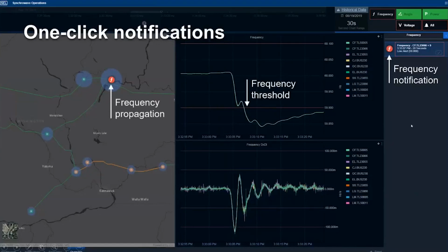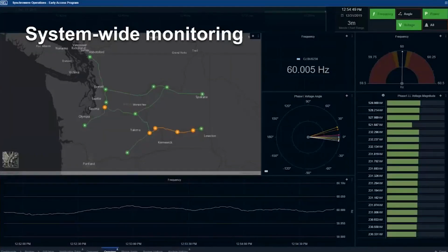In certain cases, if you have a system event like a frequency change, operators generally get bombarded by multiple alarms or messages from the SCADA system. This is a better approach because you don't get bombarded by a bunch of messages. You get one-click notification, and when you click on the notification, you get more information about what's going on in your system. So you can do system-wide monitoring. You can create custom dashboards in this software. When I say custom dashboards, you can see that a dashboard is created in this one.